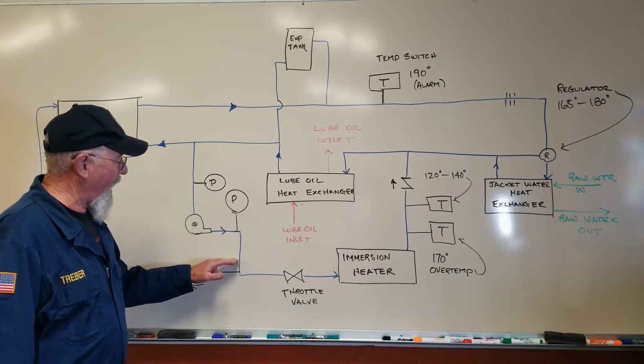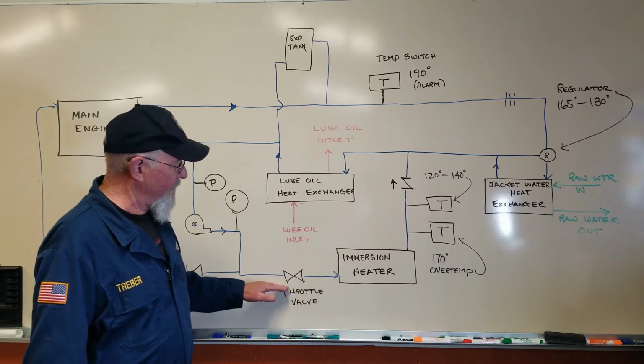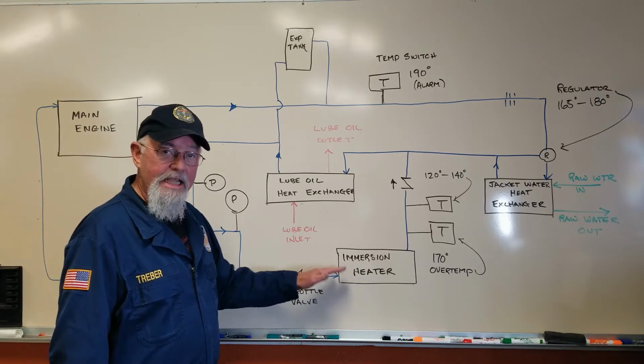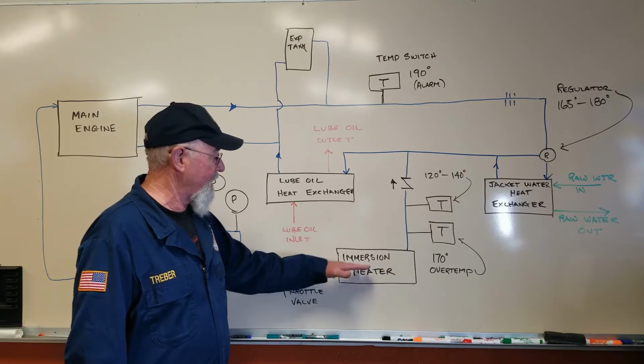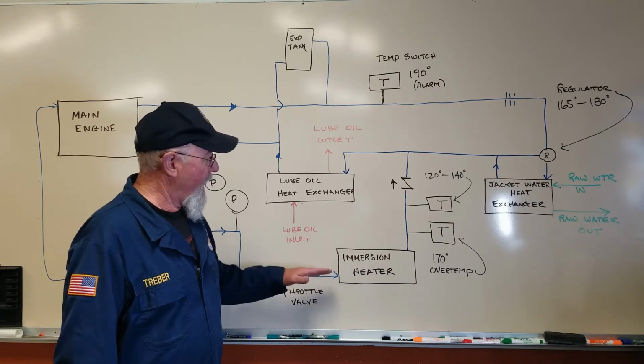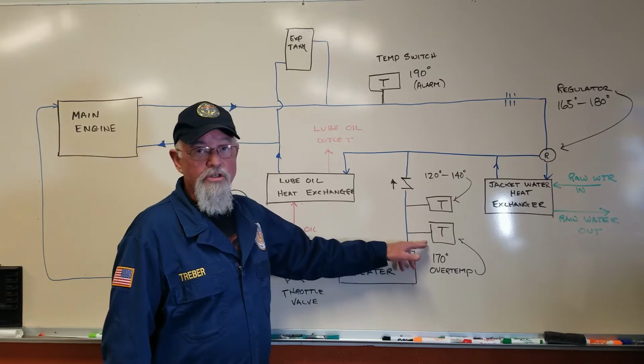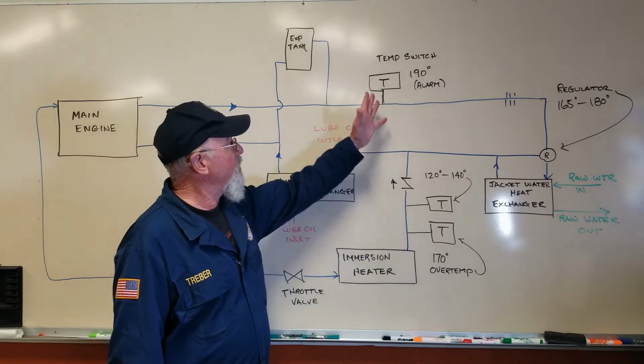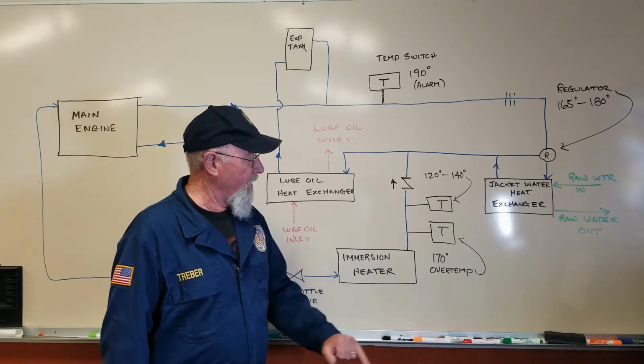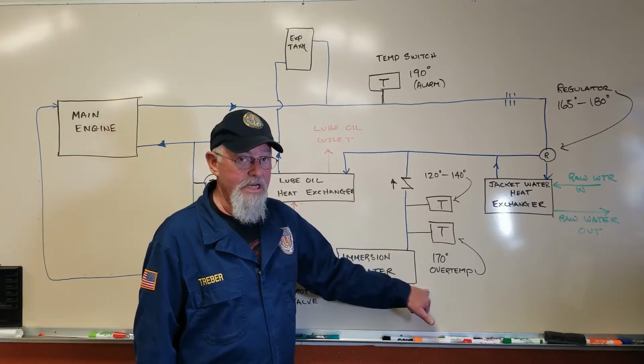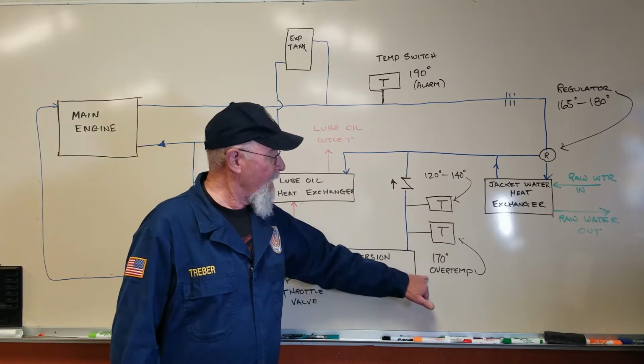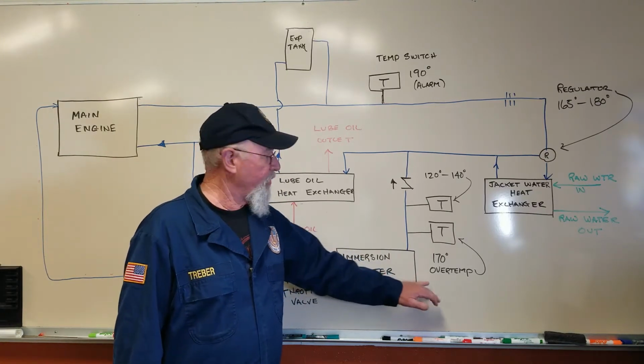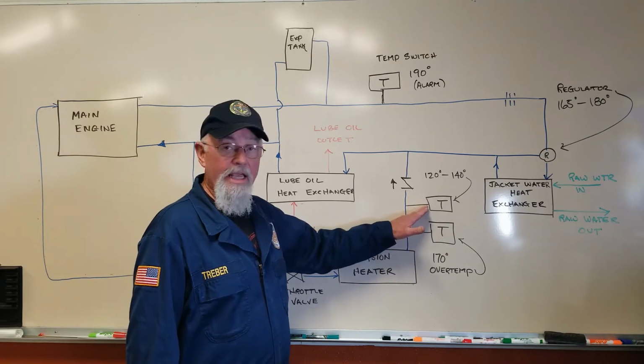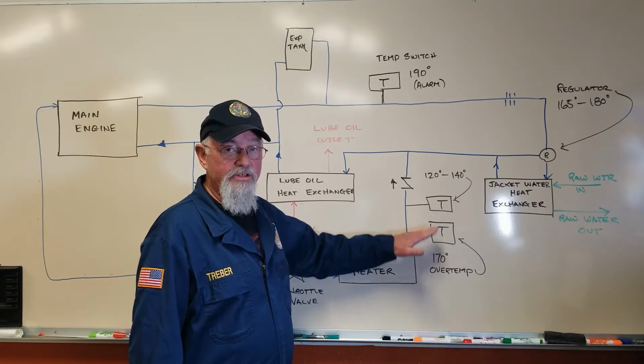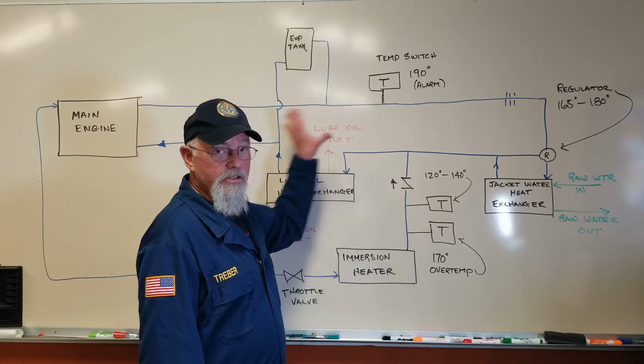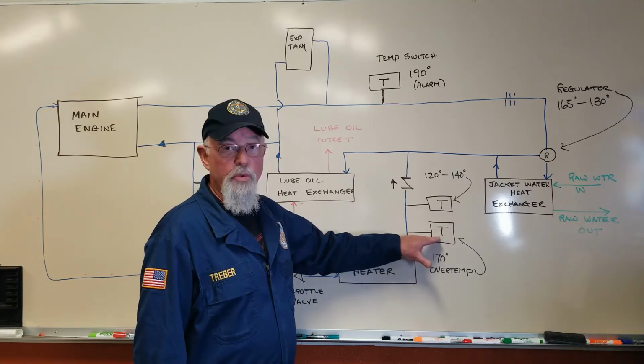So following the flow path of the jacket water, it's going to go past the throttle valve into that immersion heater, where it's going to pick up some heat because we've got the heating element energized. As it goes through the immersion heater, you'll notice there's two more temperature switches here. We've got a total of 3, but the first one here is set for 170 degrees, and these are all in Fahrenheit. That is the over temperature switch. So if there's some kind of a malfunction with the regulating temperature switch and it exceeds 170 degrees, the entire system will shut down because this temperature switch said so.